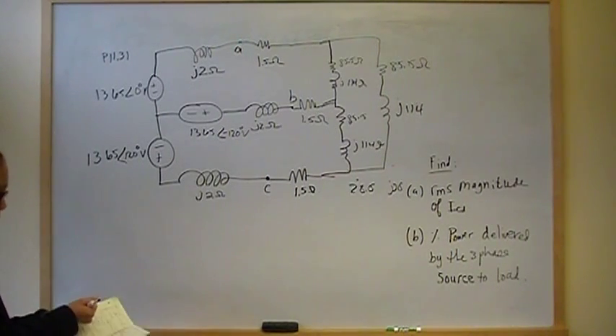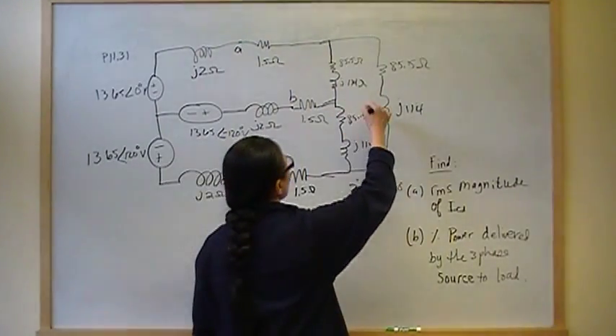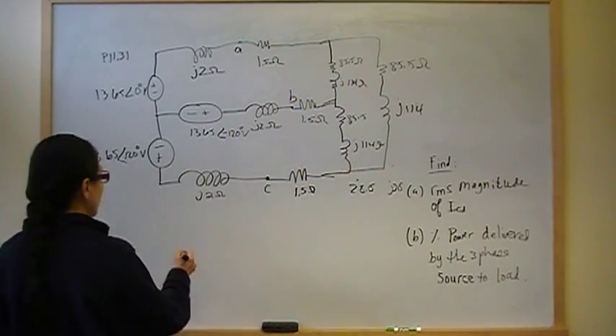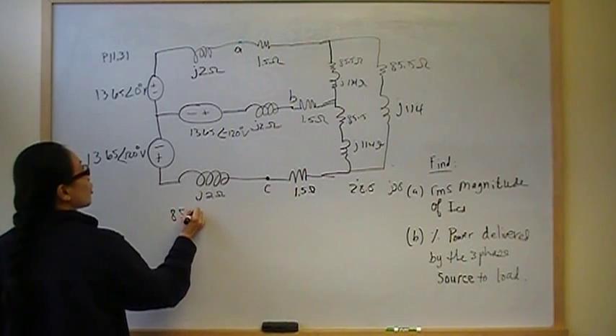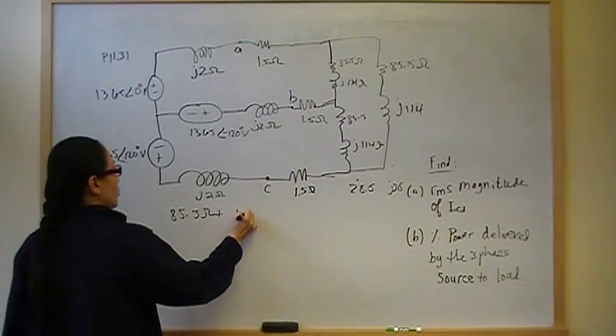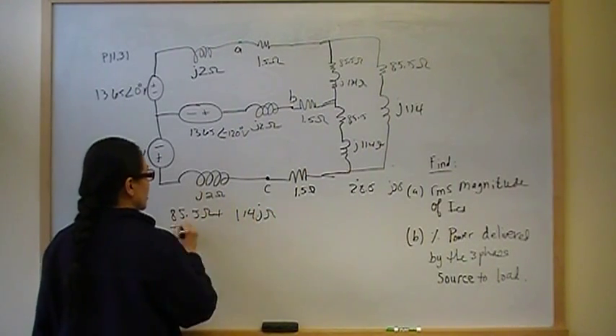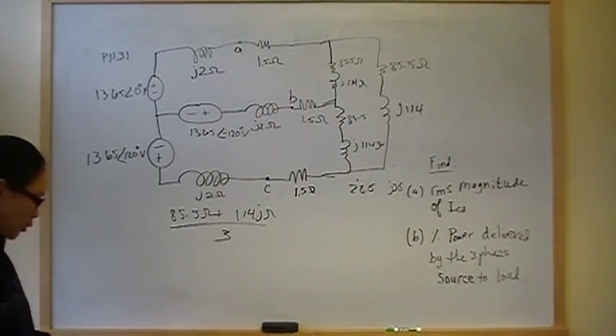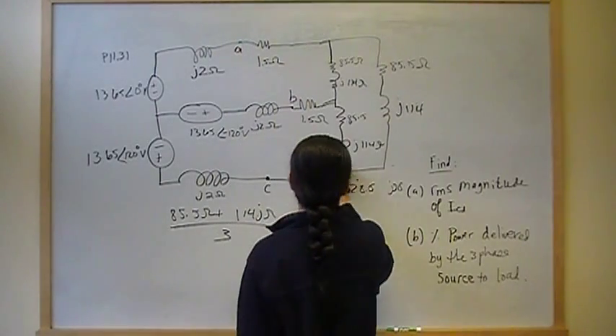So the first thing we want to do is we want to find the star equivalent of that delta connected load. And that impedance is going to be 85.5 ohms plus J114 ohms, and divide all that by three. When you do that, you should come up with 28.5 plus J38 ohms as the star connected equivalent.